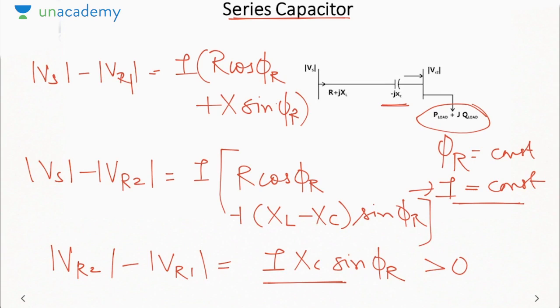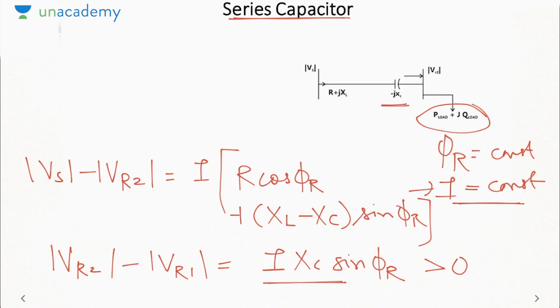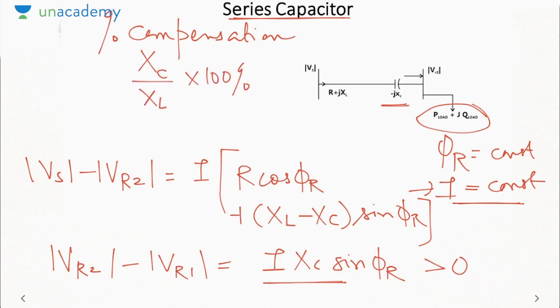How does it reduce the voltage drop? By reducing the reactance. Earlier we were reducing the current to reduce the voltage drop, but now we are reducing the reactance to reduce the voltage drop. In any case, we are reducing the voltage drop in the transmission line to improve the receiving end voltage. And in case of series compensation, we define a term called as percentage compensation or degree of compensation. It is Xc by XL into 100%. So if it is given 30% compensation, we mean that Xc is 30% of the line reactance.